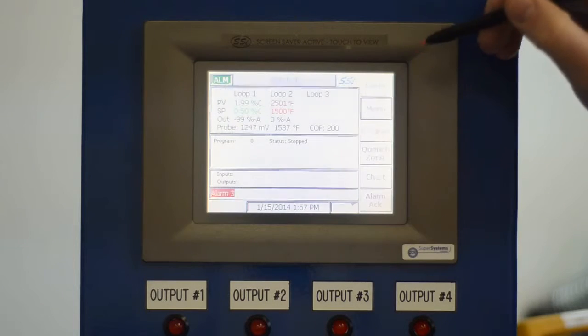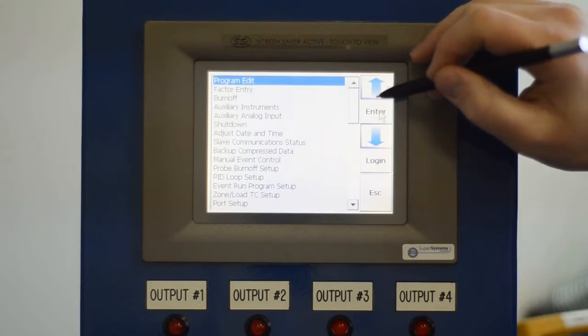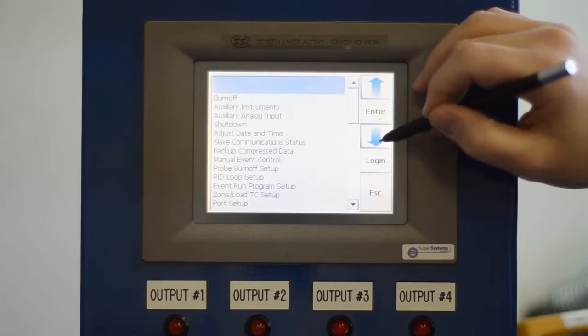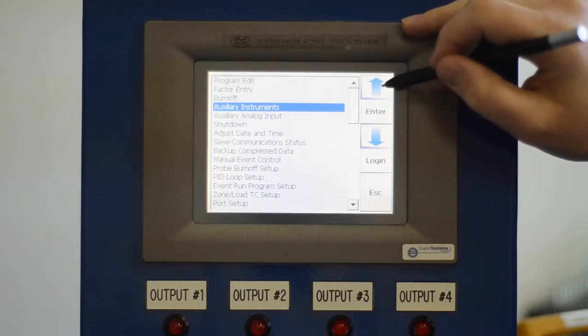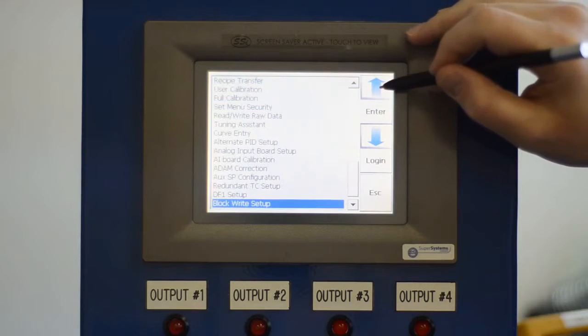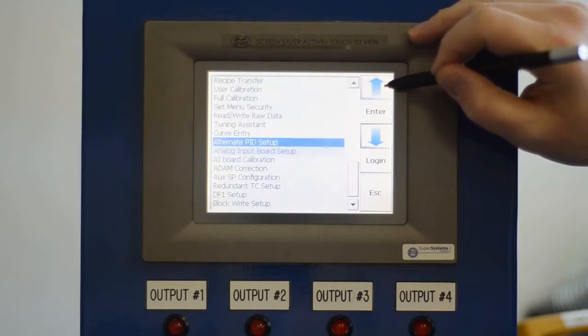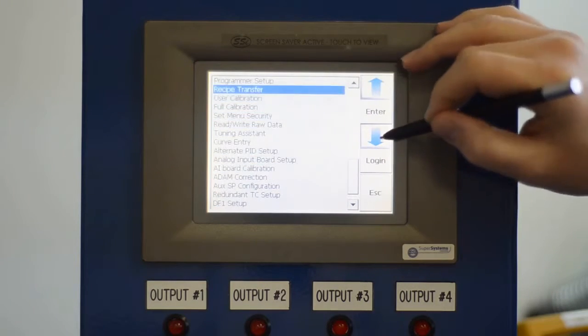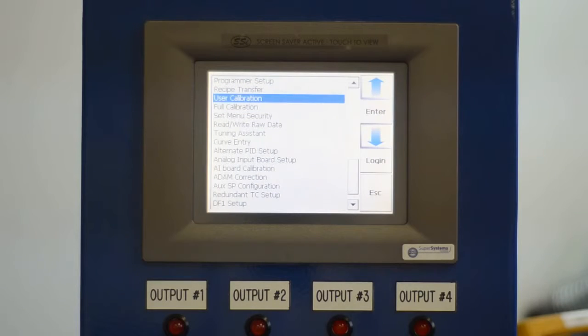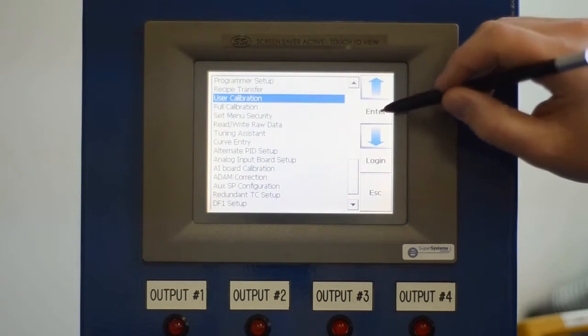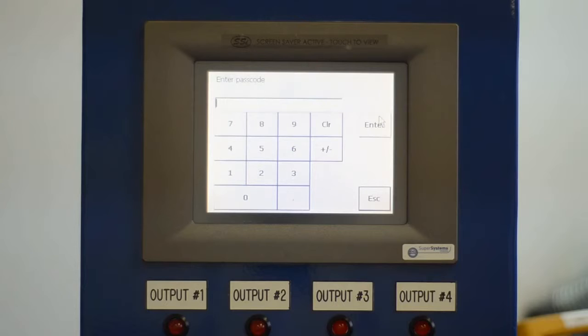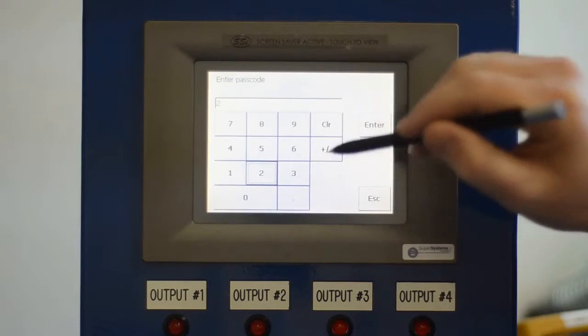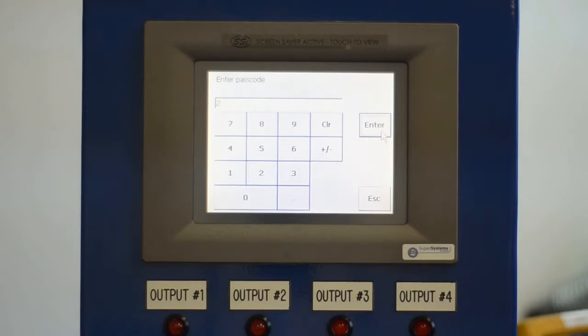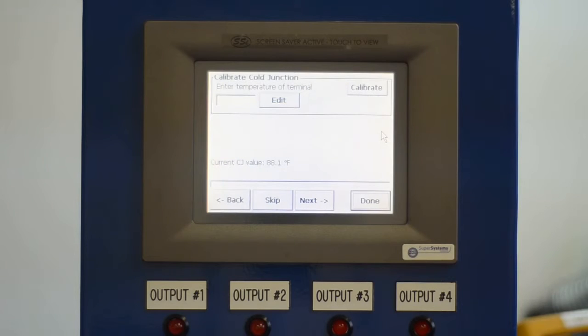So we're going to select menu, and you can either arrow down or arrow up. Since the calibration is towards the bottom of the menu, I arrow up through the bottom, and you're going to arrow until you have highlighted user calibration and select it, pressing enter. Passcode is the number 2. Enter. And this starts at the cold junction.